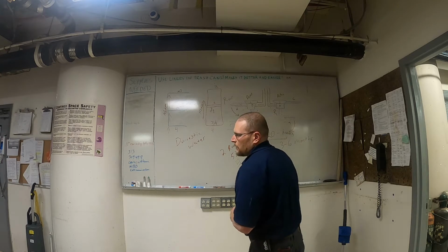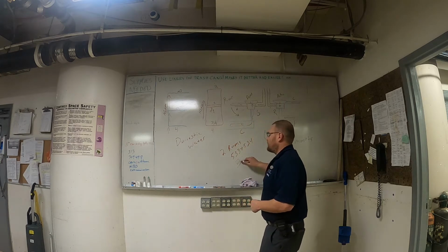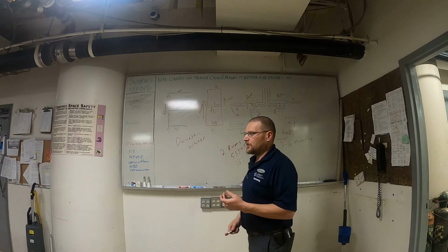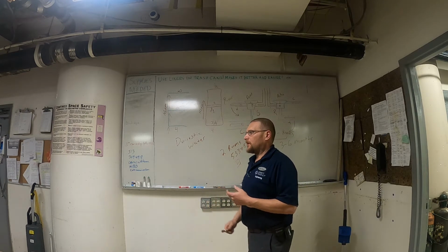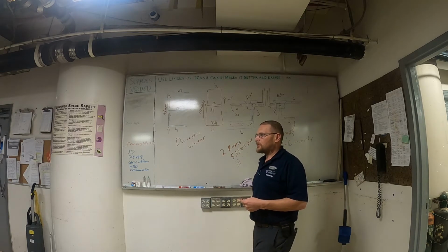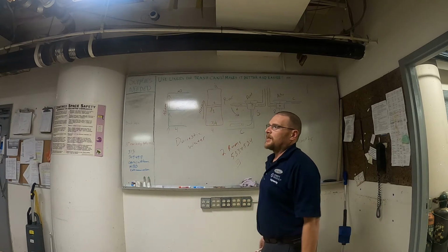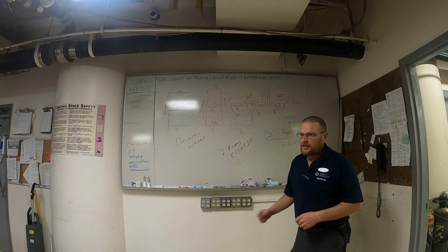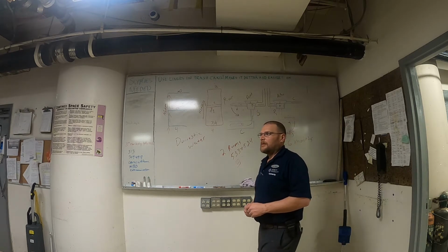With those Belimo valves, when you put in that independent thermostat, we don't have to worry about motion sensors on the doors or on the thermostat. We don't have to worry about programming the thermostat to a specific room. All that stuff. So that eliminates a lot of the headache that we have.